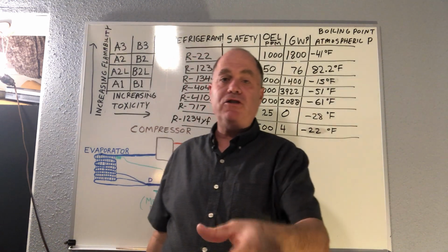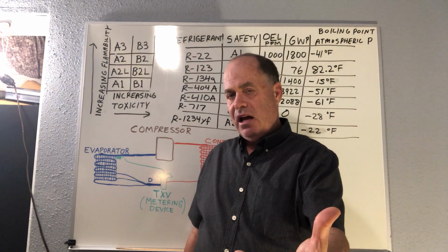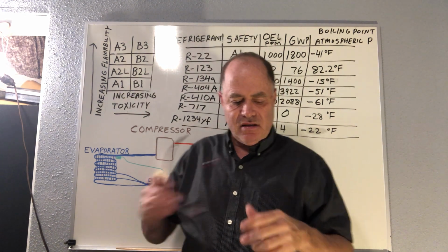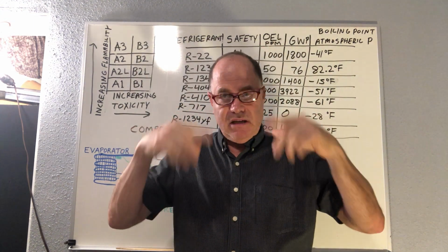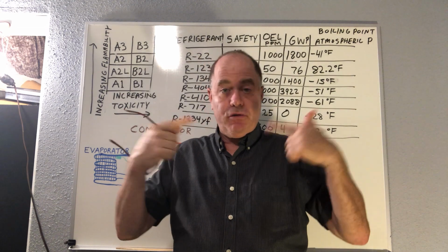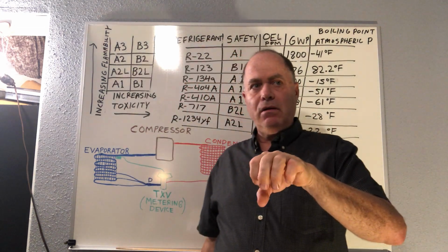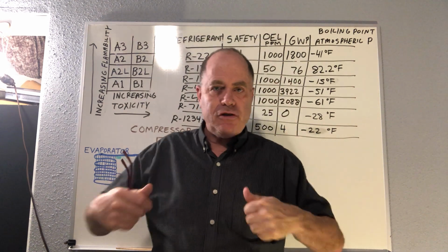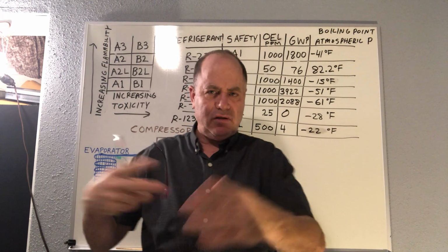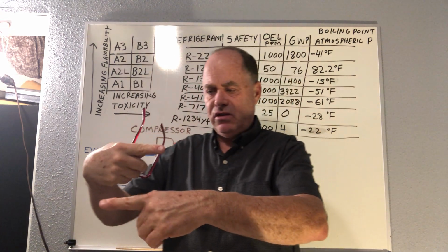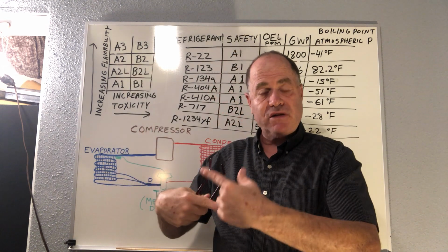What do we mean by corrupted? Usually it means an electrical failure with a compressor that has caused acid in that system. Recycled refrigerant means that you're going to take it out and put it through a recycler, which is like what you see in automotive repair shop. They have a little R2-D2 that they wheel out, and it pushes it through a couple of filter dryers. I used to have a recycler that I used, and I pushed my recovered refrigerant through there. It was kind of neat.